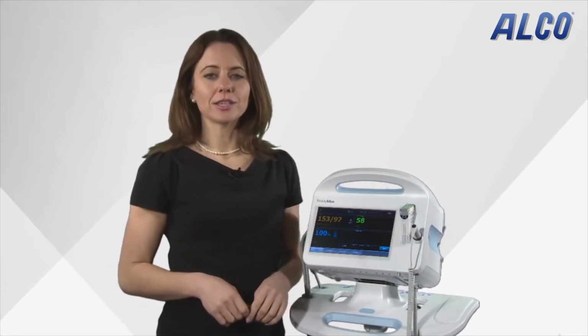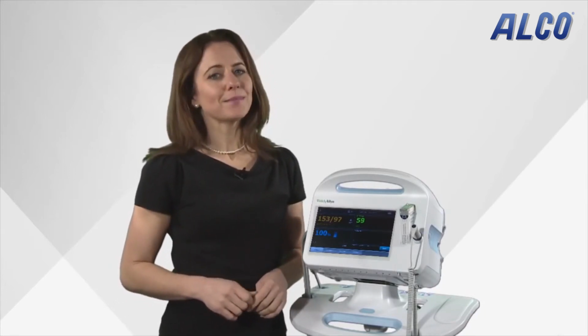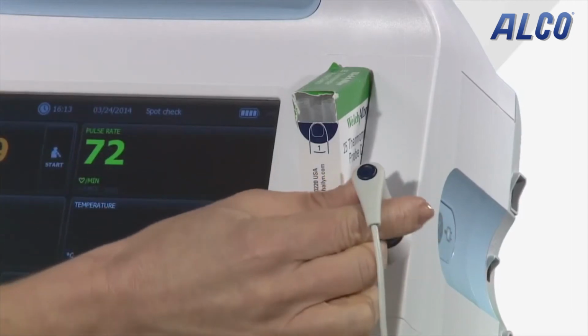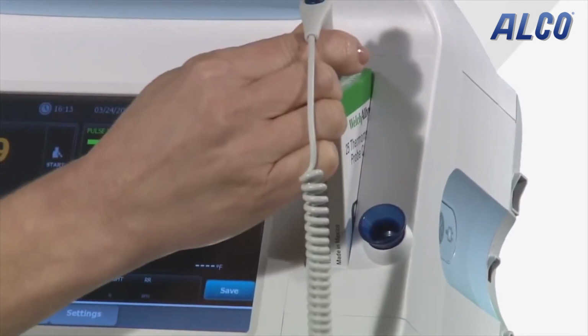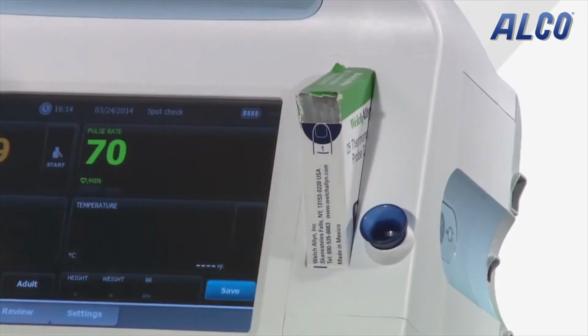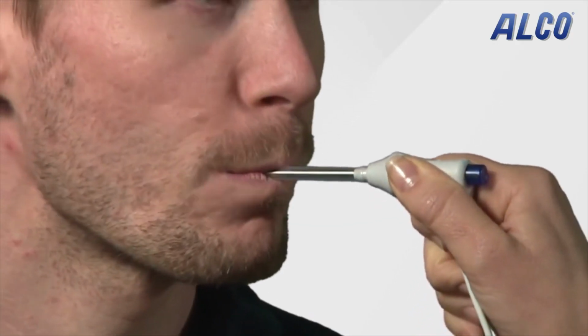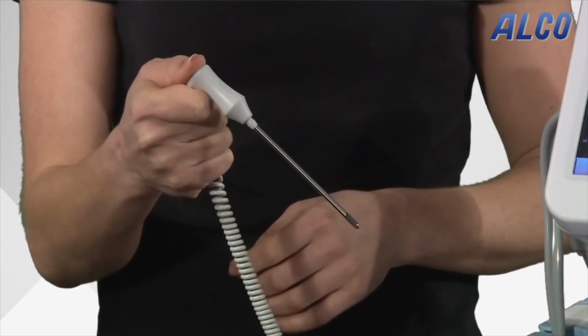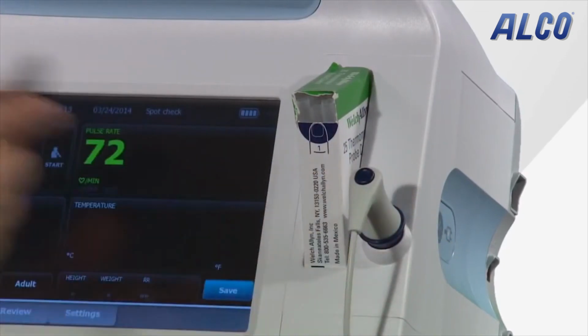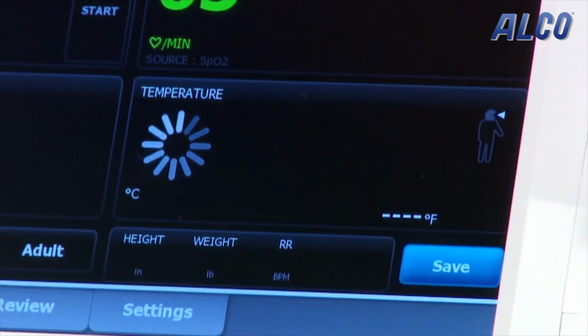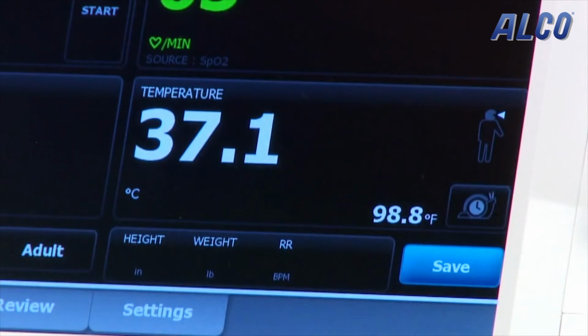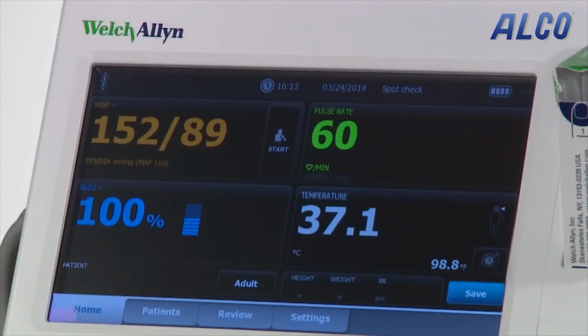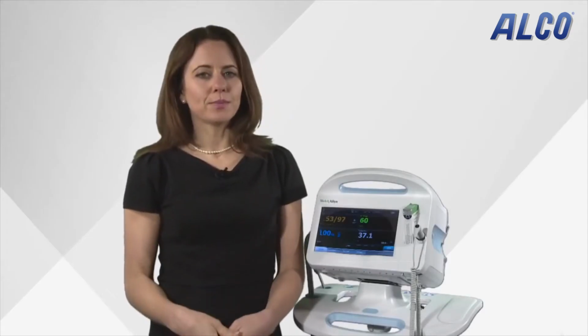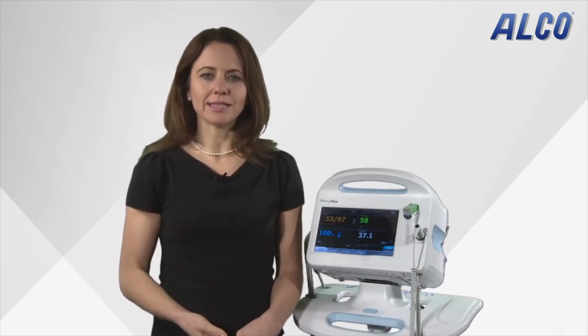If you also require the temperature, take this either using the Sure Temp or Braun tympanic thermometer, dependent on your device configuration. Attach a probe cover, take the patient's temperature, dispose of the probe cover and replace the thermometer. The temperature measurements will then appear on the screen along with the other vital signs. Remove the blood pressure cuff and SpO2 sensor when all the vitals have been captured.